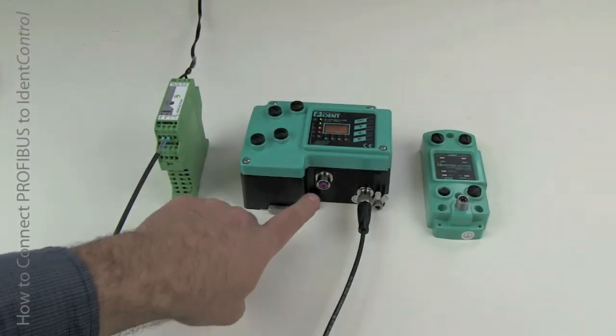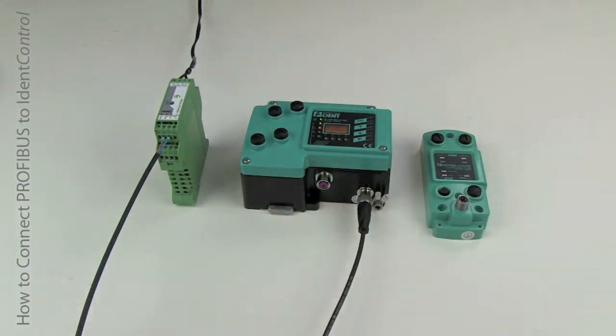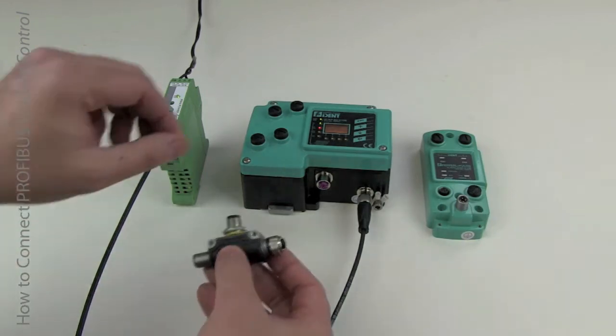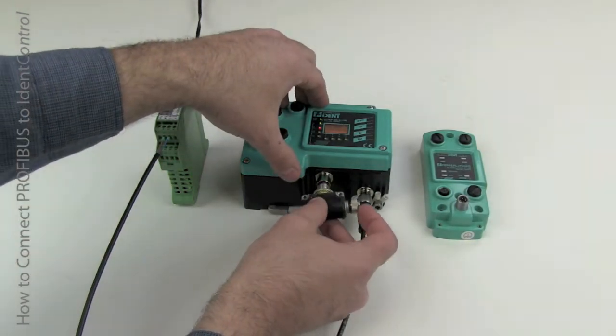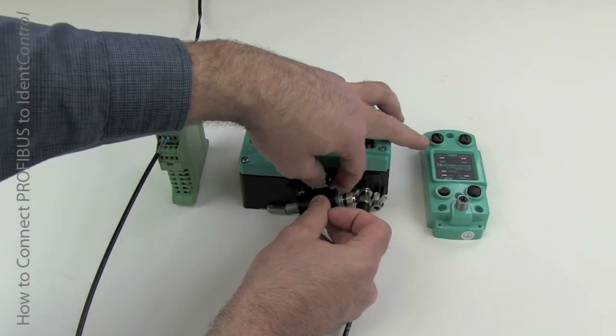The next way is to use the Profibus connection with the M12. This is the B-coded Profibus connector, and you want to connect the T or the Y cable, in this case the T, directly to the Profibus controller, never any drop length.